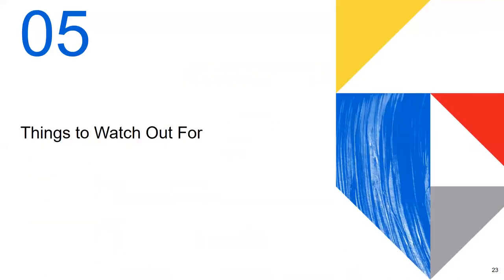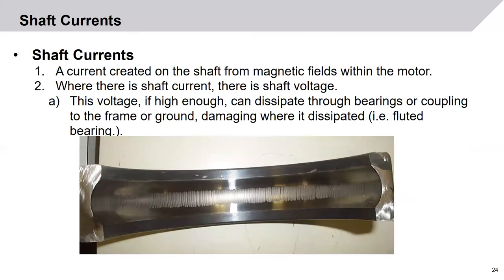Things to watch out for. First is shaft currents. A shaft current is a current created on the shaft by the magnetic fields within the motor. Where there is current, there is voltage. If this voltage gets high enough, it can dissipate through bearings, or through the coupling through the frame to ground, damaging whatever it dissipated through — for example, fluted bearings. These white match marks are where the balls of the bearing arc through the bearing race and go to ground. Once this starts, vibration will pick up and the bearing will fail if not caught quickly enough.